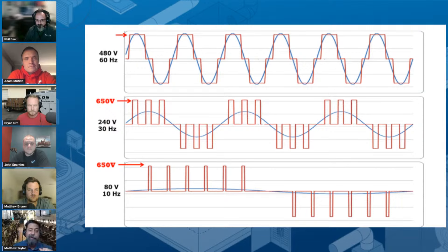We can bring in single-phase power and as long as we've got that energy source, the VFD can create DC voltage that looks like three-phase AC to that motor; it won't know the difference. When we do that, we're going to use the same horsepower — it's a 25-horse motor, it's still 25 horse. When sizing the wires to that VFD, we use the rules of three-phase power and the square root of three. But the single-phase wire feeding the VFD will carry that same horsepower on two wires instead of three, so amps are going to be higher — that breaker and wiring feeding the VFD is actually going to be larger than what runs the motor.